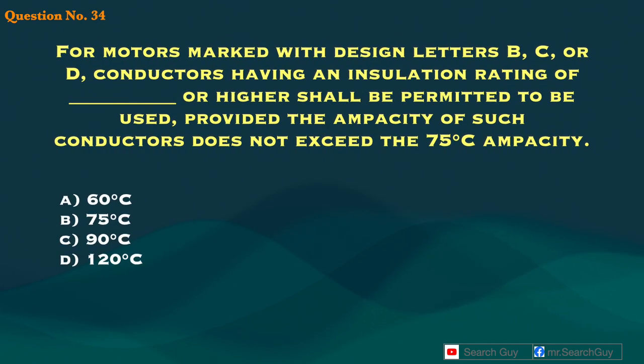Question 34. For motors marked with design letters B, C, or D, conductors having an insulation rating of blank or higher shall be permitted to be used, provided the ampacity of such conductors does not exceed the 75°C ampacity. A. 60°C. B. 75°C. C. 90°C. D. 120°C. Answer: B. 75°C.